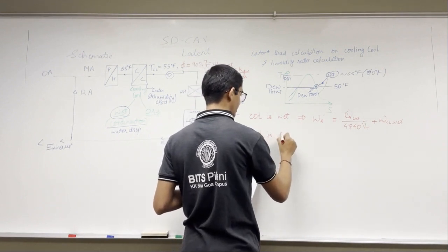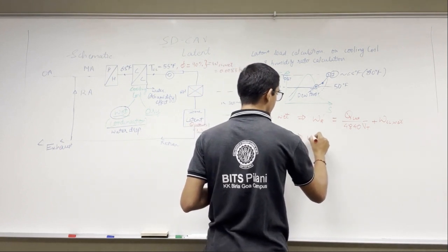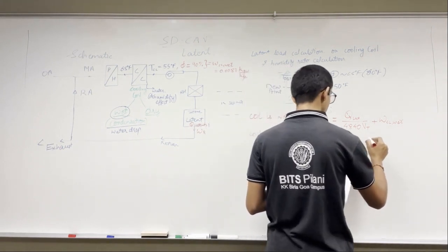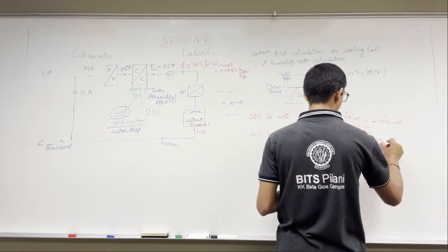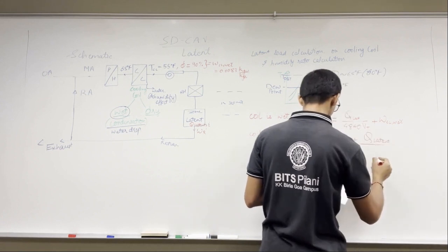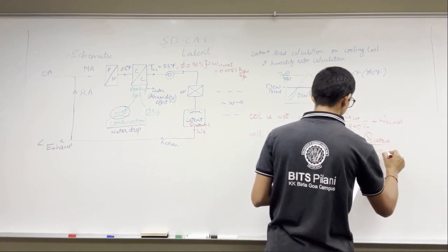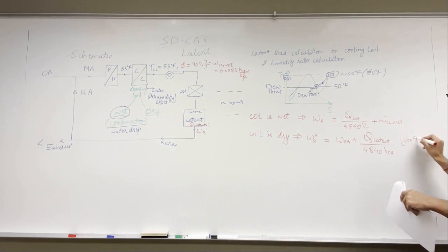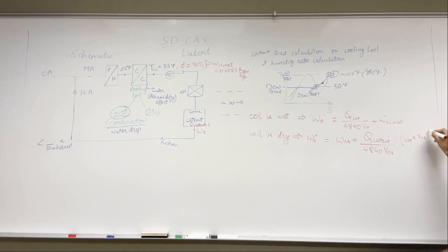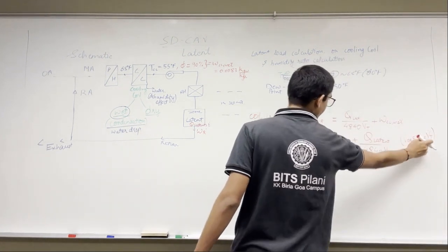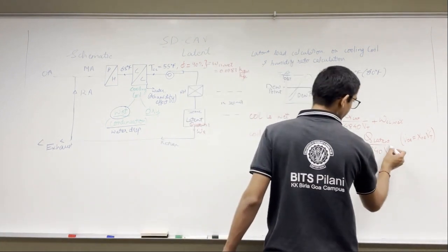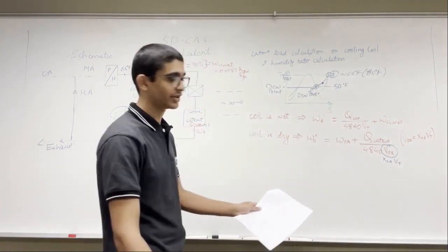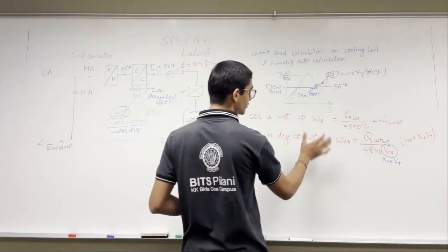If the cooling coil is dry, there is another condition: omega_r double prime, given as omega_OA plus Q_latent divided by 4840 times V_OA. V_OA is also equal to X_OA times V_T, since X_OA is defined as V_OA divided by V_T. So we can substitute X_OA times V_T in place of V_OA. If V_OA is given directly, we can use that value. Those are the two formulas we have.